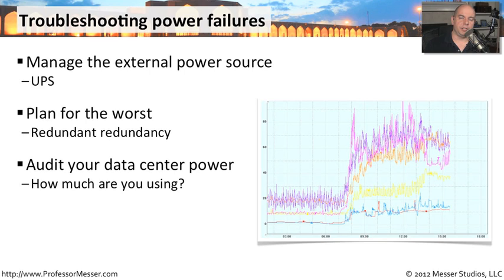I've been in previous positions where we were in the data center and suddenly lost entire racks full of power. Everything in the rack suddenly powered off because we did not properly audit the amount of load being used by all of those different components. We overloaded the circuit, the circuit had a break, it suddenly stopped, and everything in that rack went black immediately.